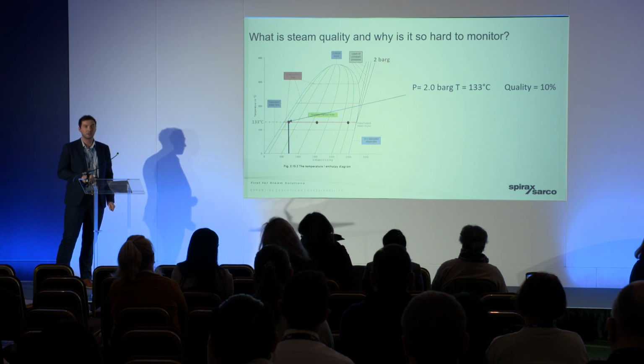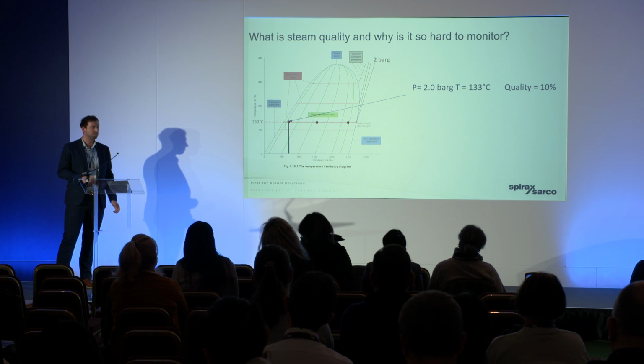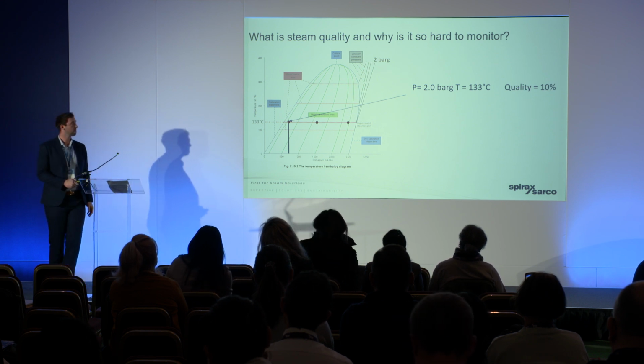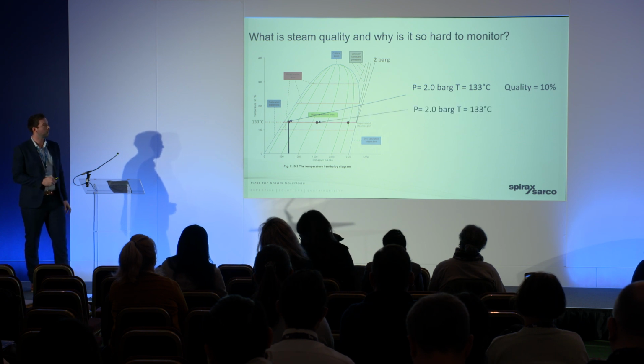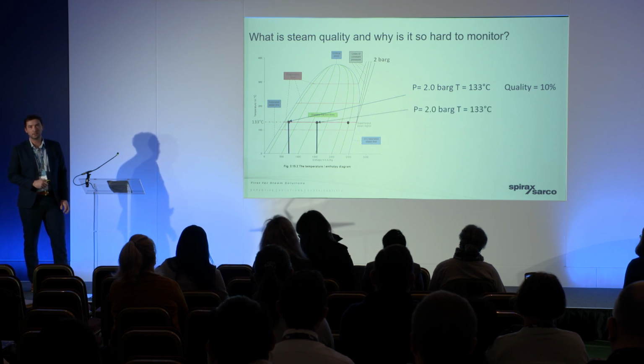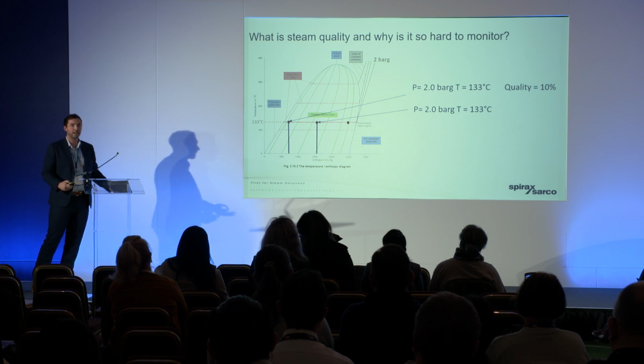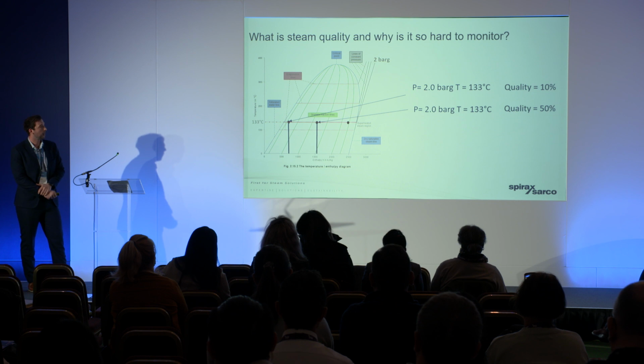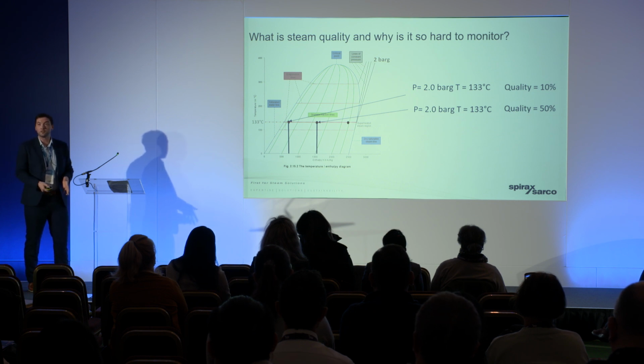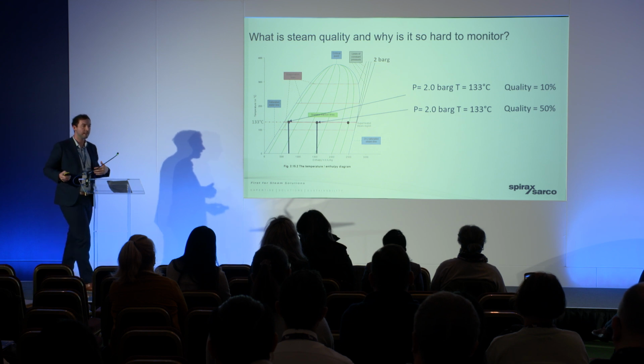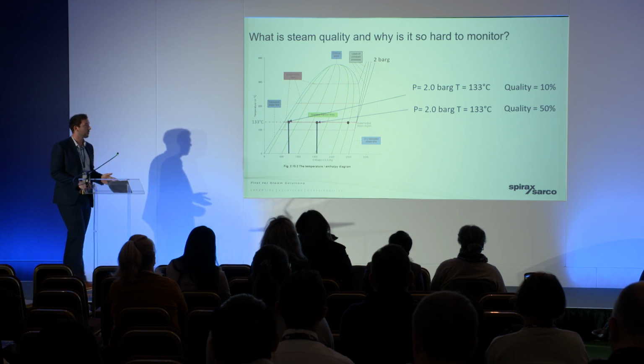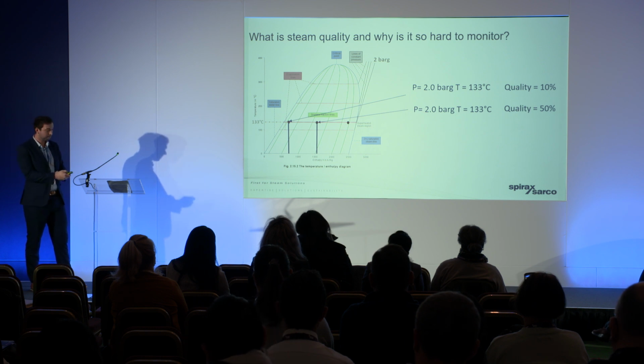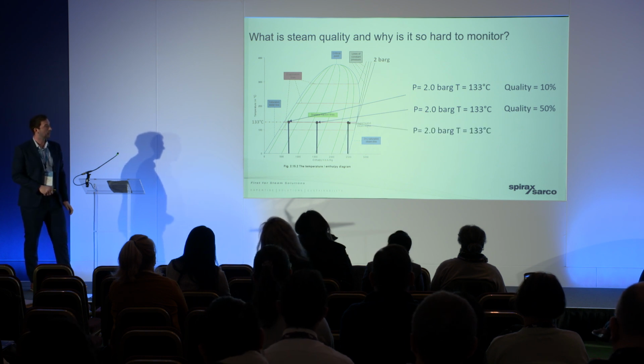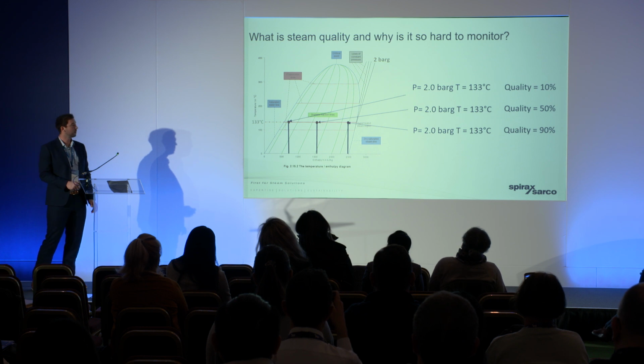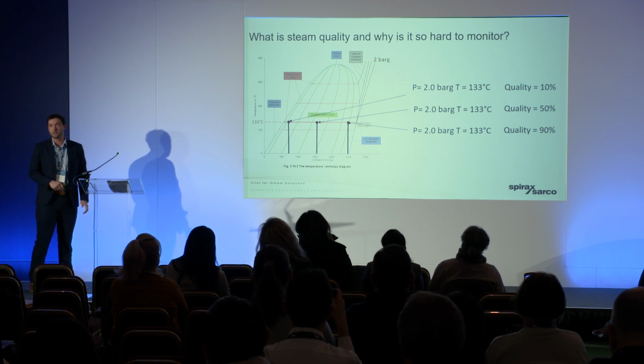It's pretty much entirely water. Our energy content is right down here, 600 kilojoules per kilogram. Okay, still quite a lot, but it's not as much as we could have. So let's stay at the same pressure and temperature. Let's make our steam better quality, so drier, less water content, more vapor. Well, we've now got over 1,500 kilojoules per kilogram. So for pumping the same mass of fluid down that pipe, we've got 3 times the energy content in the same pipe. Now let's go one better. Let's go up to 90% quality. We've got 2,500 kilojoules per kilogram. So 4 times our initial energy content in the same pipe.